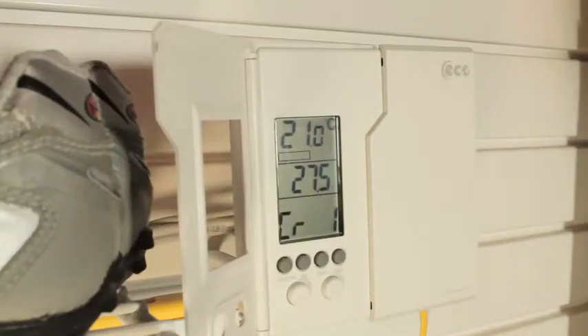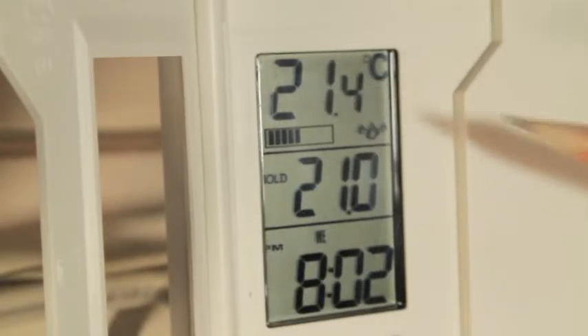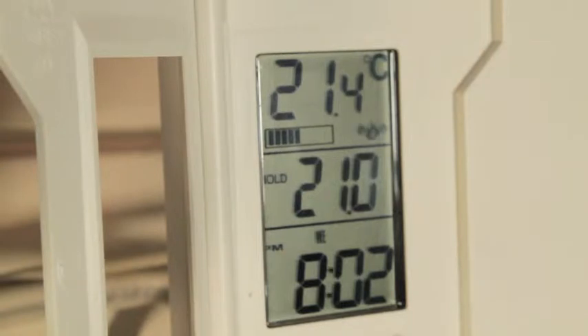Pressing set again will advance you to the next option. The next option is the cycle rate. The default cycle rate appears as CR1 and this is a good setting for an electric baseboard heater. This rate allows the thermostat to send pulses of electricity to the baseboard to maintain a constant and efficient temperature. When the thermostat is using heat cycling, you will notice the power output level will change.